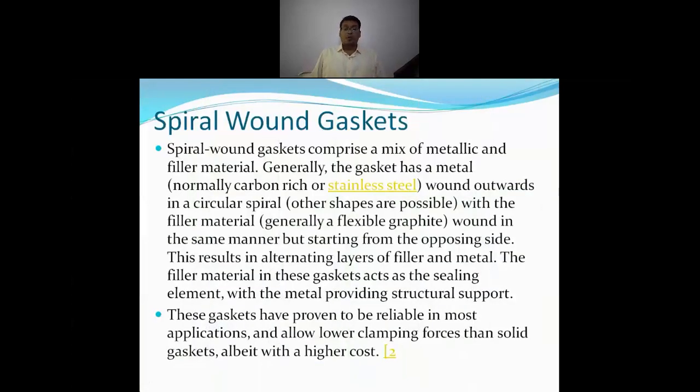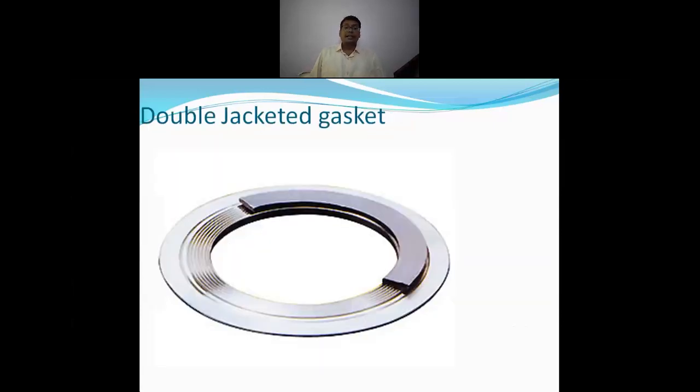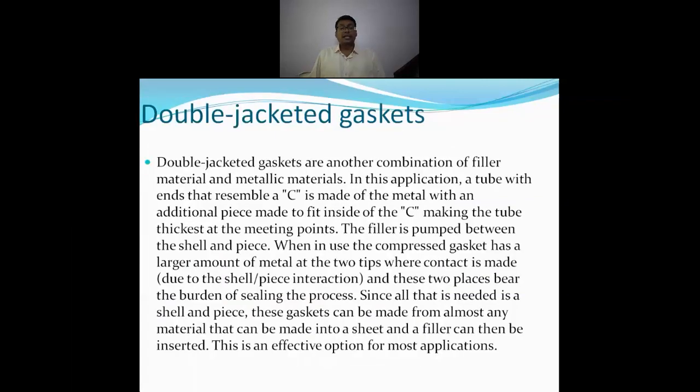These gaskets have proven to be reliable in most applications and allow lower clamping forces than solid gaskets, but at a higher cost because they are specially designed. Then double jacketed gaskets. These gaskets are double jacketed. So one layer is available and there is a second layer also. These double jacketed gaskets are another combination of filler material and metallic gaskets.